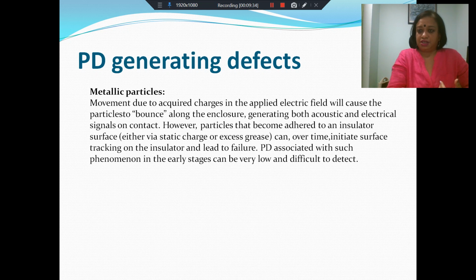There is also a possibility that some particles may be sticking to the insulator surface, either because of static charge, or because of some kind of grease, or because of a manufacturing defect. They're not hopping around, but they cause local field intensification. Over time, this local field intensification around these fixed particles can cause surface tracking, treeing might happen, and ultimate failure of the insulator might happen. The partial discharges associated with fixed particles embedded in insulators are of very low magnitude. In the early stages, they're very low and difficult to detect. Only when they go on to a situation where they're already hazardous do the signals increase and we may be able to detect them.